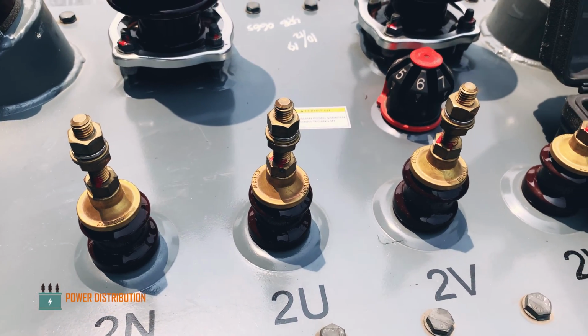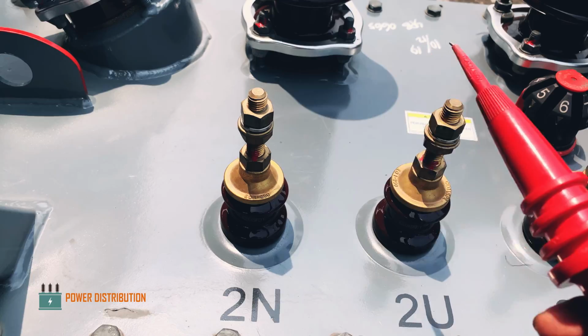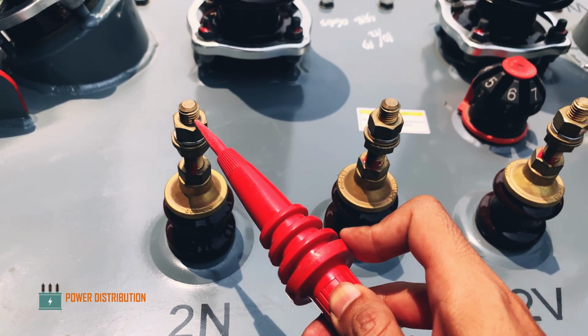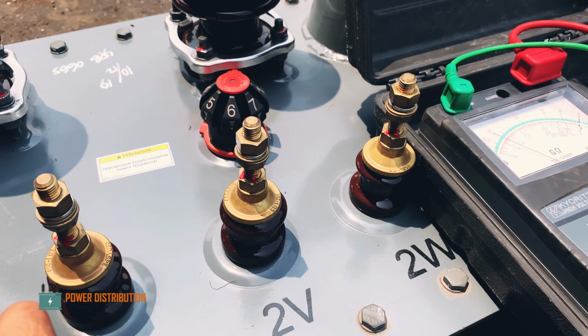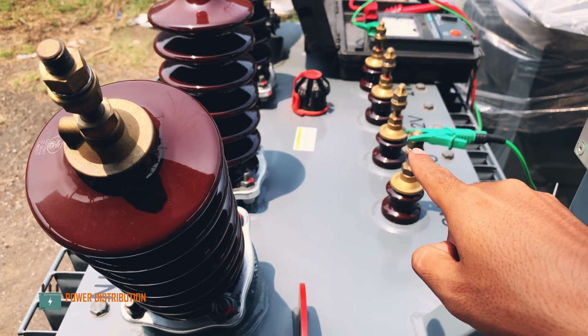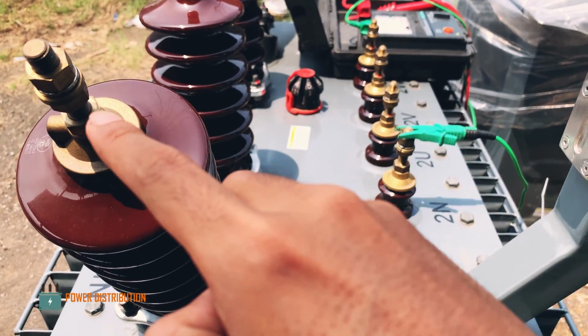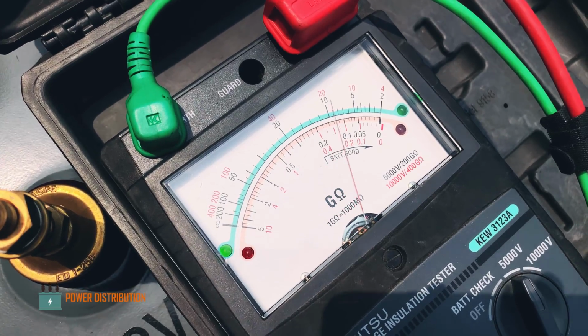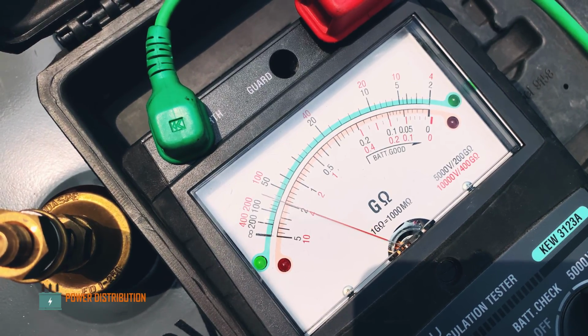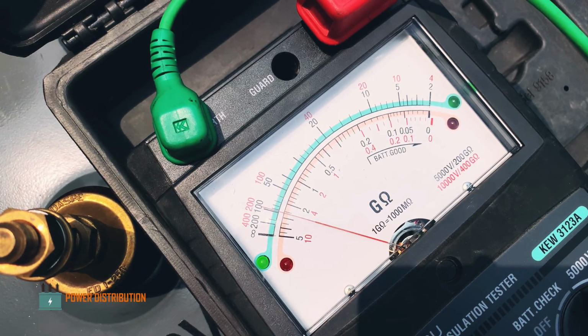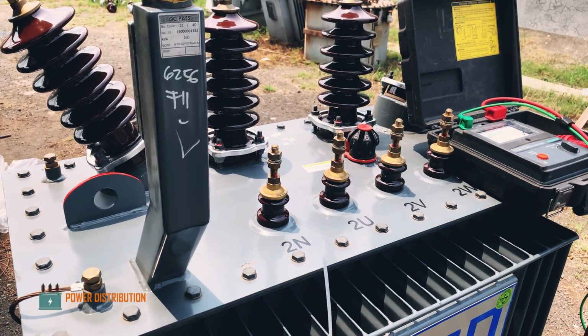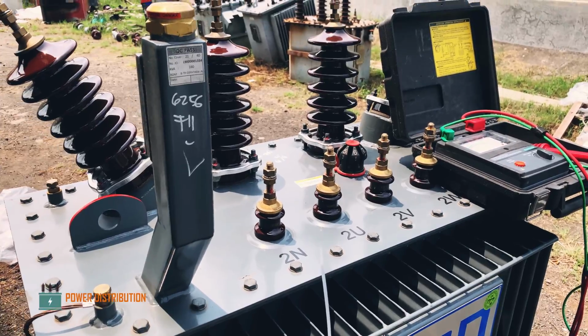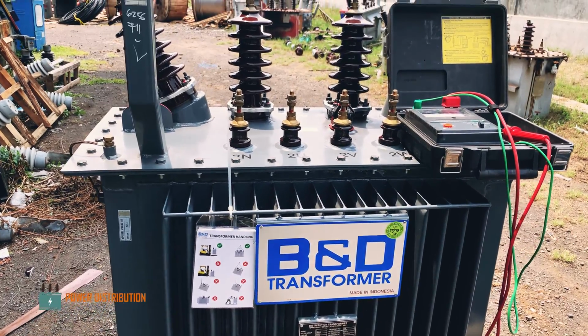Next, the secondary windings. Touch the terminal slowly and read the measurement. And last but not least, measure the resistance between the primary and secondary. The reading is around 60 to 70 gigaohm, which is pretty good. So the insulation resistance of the transformer is very good.